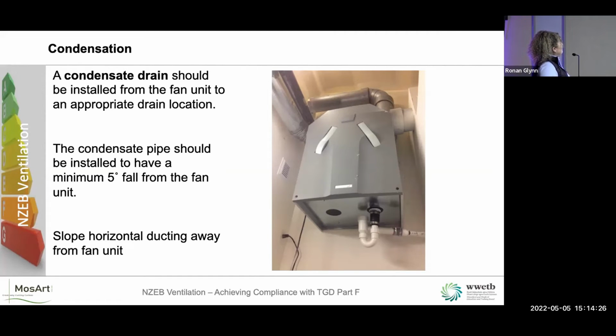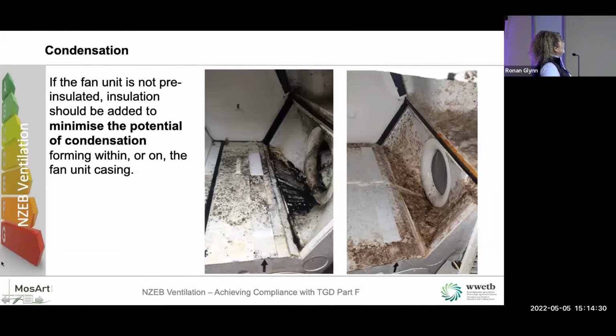Condensation. Okay, so if the fan unit is not pre-insulated, insulation should be added to minimize the potential of condensation forming within or on the fan unit casing. So you can see here there is condensation running down. You can see the little trails of it. This was a unit, the one further back on the slideshow, that you couldn't change the filters. So because the filters hadn't been changed, all the dust and dirt was ending up in the unit. So this is the supply end of it. Mold reproduces by producing these little spores and it spits them out. So that was going into the supply rooms.